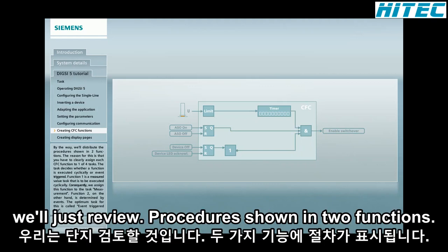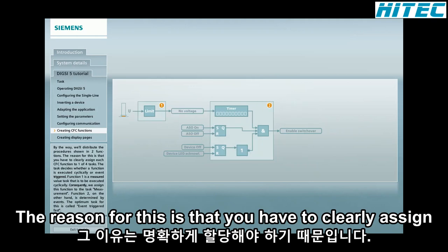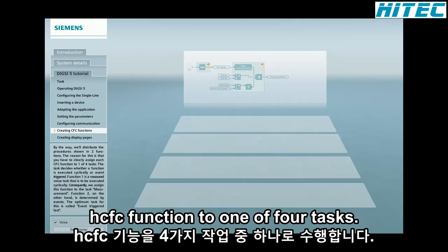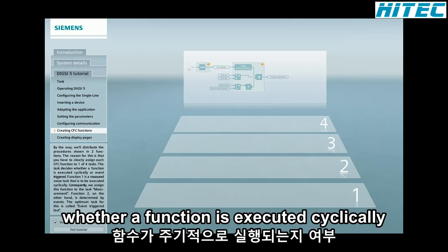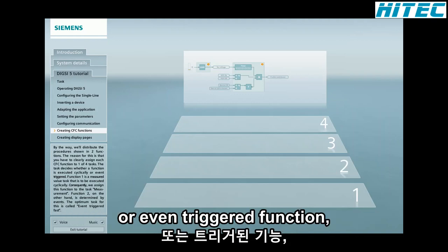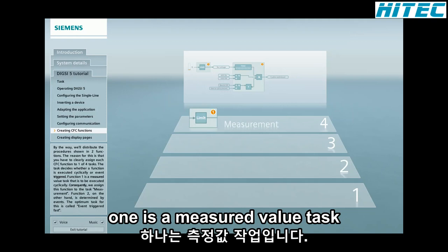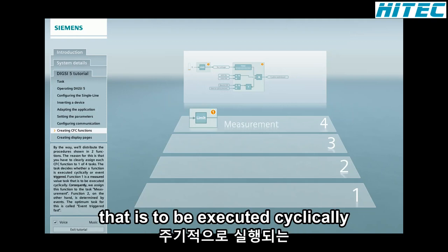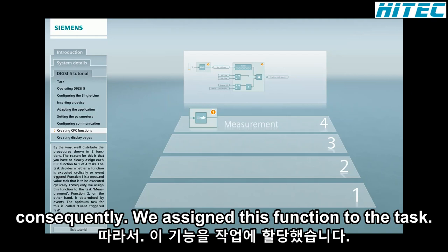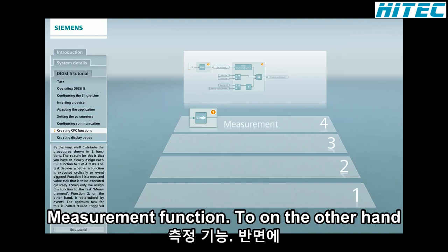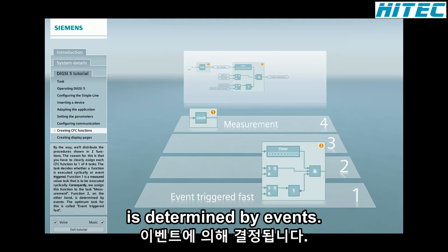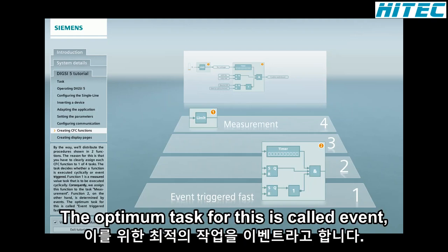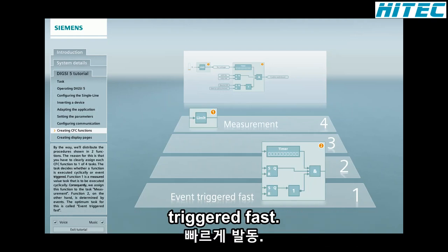By the way, we'll distribute the procedures shown in 2 functions. The reason for this is that you have to clearly assign each CFC function to one of 4 tasks. The task decides whether a function is executed cyclically or event-triggered. Function 1 is a measured value task that is to be executed cyclically. Consequently, we assign this function to the task measurement. Function 2, on the other hand, is determined by events. The optimum task for this is called event-triggered fast.